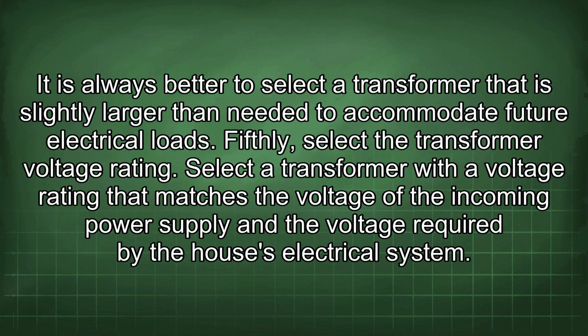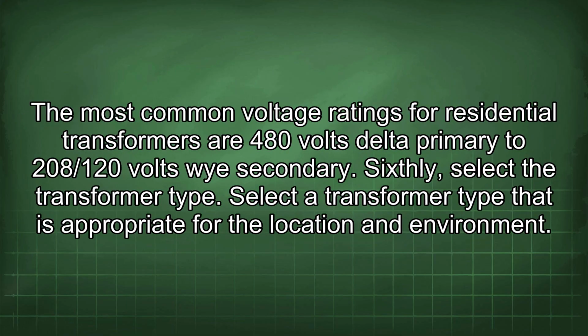Fifthly, select the transformer voltage rating. Select a transformer with a voltage rating that matches the voltage of the incoming power supply and the voltage required by the house's electrical system. The most common voltage ratings for residential transformers are 480 volts delta primary to 208/120 volts wye secondary.